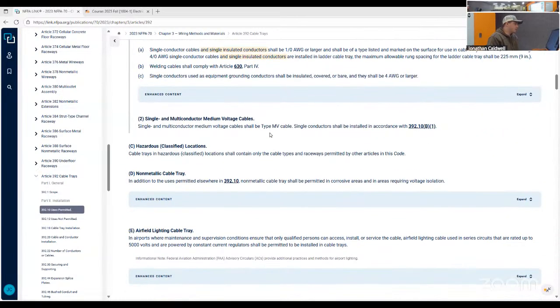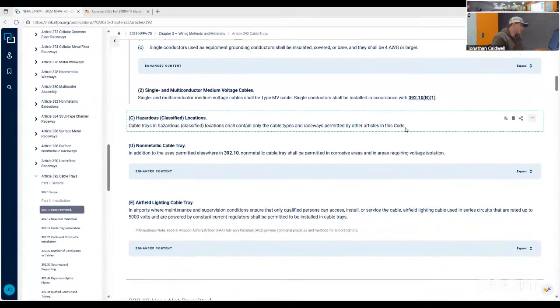Okay, single and multi-conductor cables are still installed in accordance with 392.10(B)(1), so it follows the exact same article. And then hazardous classified locations shall contain only the cable types and raceways permitted in other articles. So as you can tell, cable tray does not care. Obviously, you're not going to use steel tray in an acid area, right? Because it'll just get eaten away. That's why we use fiberglass tray, and we actually use a higher type of fiberglass. There are 2 types for that tray: vinyl ester and polyester. We use vinyl ester because it's thicker and more dense, and it's just a better product, and the coating they put on it is a lot better too.